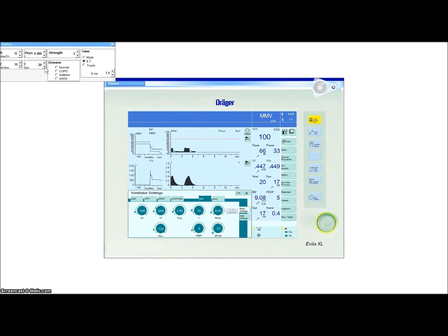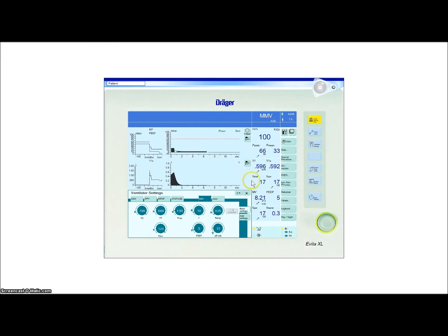But let's say the patient starts to go unconscious. His breath rate slowly goes down. Go ahead and go up to 600 for the patient spontaneous effort. So it's going down. Now watch the mandatory frequency. If it goes all the way down to 3, notice, the minute volume is going to start going down. And it's really going down. So what happens to the mandatory frequency? So there's no more spontaneous effort. Watch the mandatory frequency. Watch the minute volume. Mandatory frequency is going up.